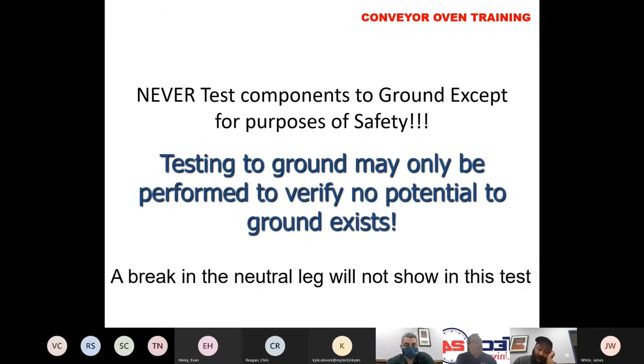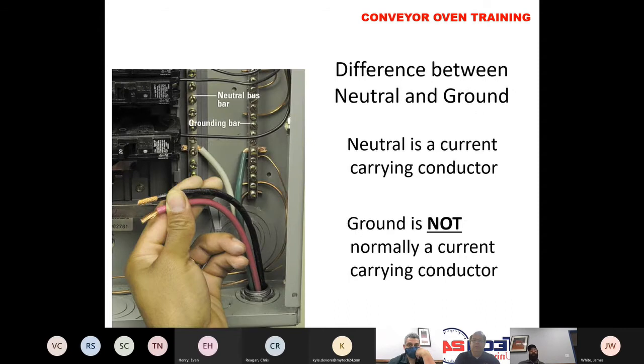Never test components to ground except for purposes of safety. So when we're doing our testing, our troubleshooting, make sure that we're referencing neutral or another leg of electricity and not ground. If we have a break in the neutral line that is causing us problems, we're not going to see that if we're referencing ground. So only use ground to test to make sure there's no electricity present for safety reasons.